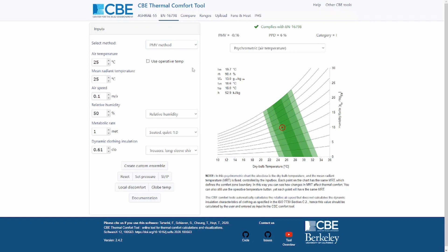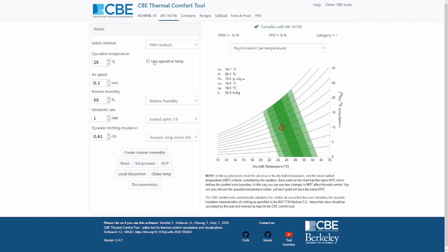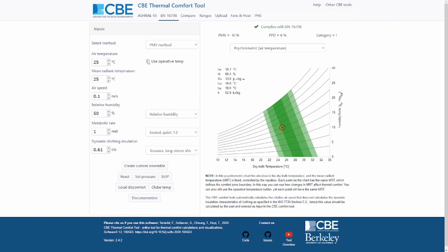We need to provide the six input parameters required to calculate the PMV. Sometimes these can be five if we toggle the 'use operative temperature' switch, which lets us input the operative temperature instead of separate air temperature and mean radiant temperature values. If you're unfamiliar with any variable, click on its name to be redirected to Wikipedia or our website. I would also encourage you to read ISO 7730, which explains how to measure each variable.